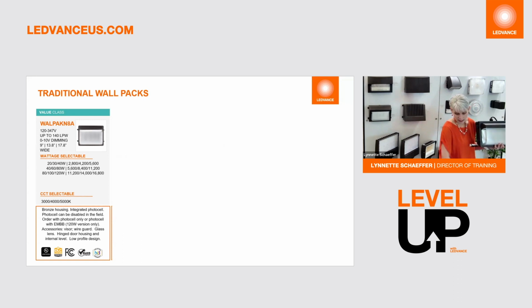And because this is a glass lens, you also have the opportunity to add the wire guard, which is important in some applications too. The other nice thing about this particular product is that it has a really nice, slim, low profile design. It still meets the footprint of a traditional wall pack. So if you ever take off a wall pack, sometimes there's discoloration. This is going to hide that, but it's not going to stick out nearly as far from the wall either. Now, by the way, this is not ADA compliant. Okay, I know sometimes we have questions on that. But anyways, so this is our value class wall pack.